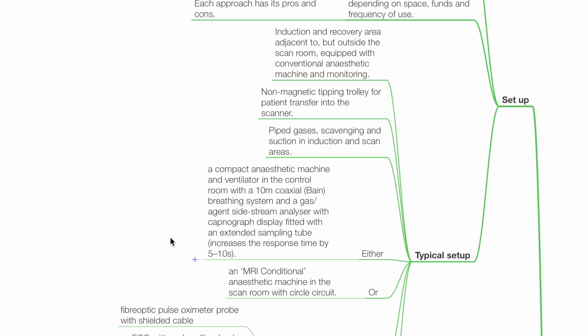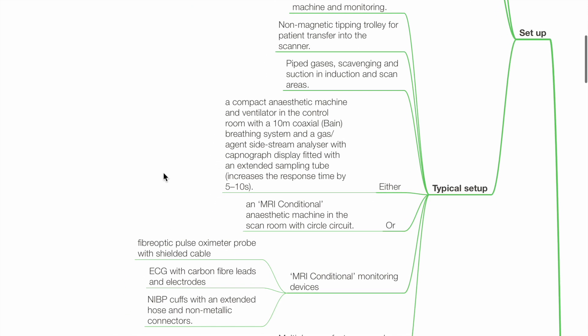Typical setup includes an induction and recovery area adjacent to but outside the scan room, equipped with a conventional anaesthetic machine and monitoring. Use a non-magnetic tipping trolley for patient transfer. Piped gases, scavenging, and suction should be available in both induction and scan areas. Either a compact anaesthetic machine in the control room with a 10-metre coaxial Bain breathing system, and a gas agent sidestream analyser with capnograph display fitted with an extended sampling tube.